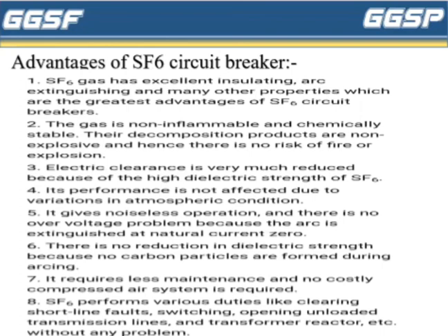Advantages of SF6 circuit breaker are: First, SF6 gas has excellent insulating, arc extinguishing and many other properties, which is the greatest advantage of SF6 circuit breaker. Second, the gas is non-inflammable and chemically stable. Its decomposition products are non-explosive and hence there is no risk of fire or explosion. Third, electrical clearance is very much reduced because of the high dielectric strength of SF6 gas. Fourth, performance is not affected due to variation in atmospheric condition.